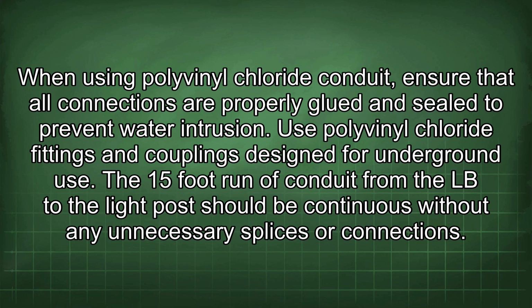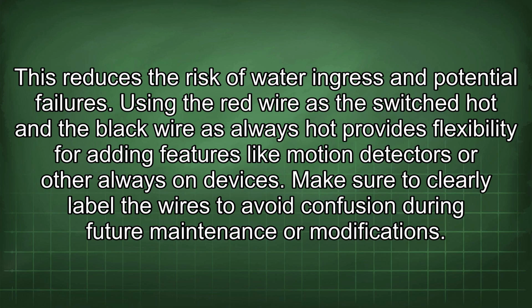The 15-foot run of conduit from the LB to the light post should be continuous without any unnecessary splices or connections. This reduces the risk of water ingress and potential failures. Using the red wire as the switch hot and the black wire as always hot provides flexibility for adding features like motion detectors or other always-on devices. Make sure to clearly label the wires to avoid confusion during future maintenance or modifications.